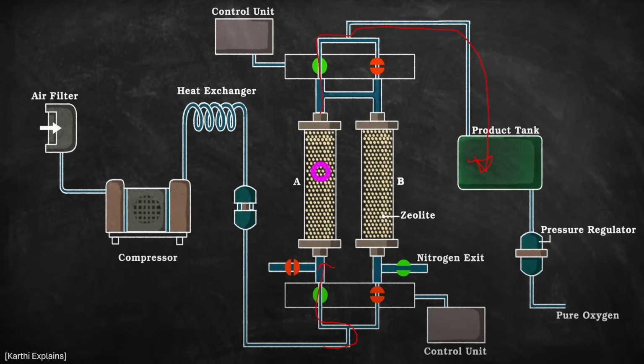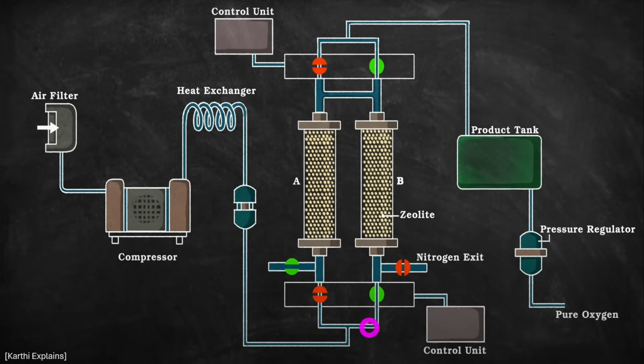At this point, the system is going to switch, and it's going to change the valve, allowing the air to go through the other tank, B in this case, and then it's going to open this valve. Now there's high pressure in here because it was pressurized just a moment ago, and then this tank over here is closed, allowing the nitrogen to exhaust back out. And the cycle is going to go back and forth, and it's going to repeat doing that. This allows tank A to be discharged while tank B is purifying oxygen again. And this process can, of course, go on indefinitely. And there's going to be some control units required to close and open these valves. But really, the process is pretty straightforward.